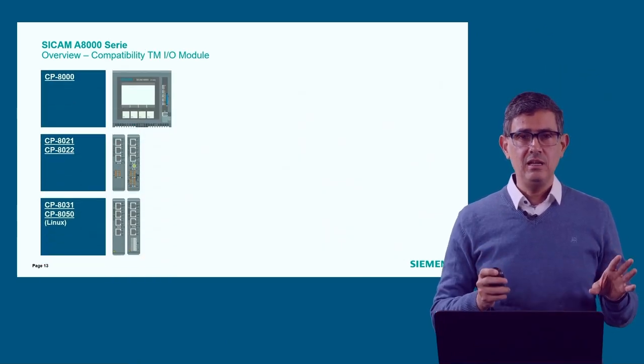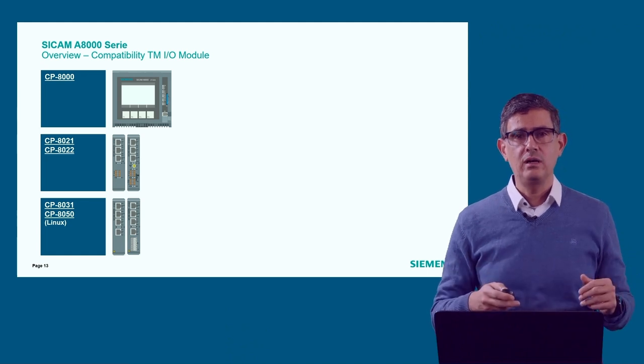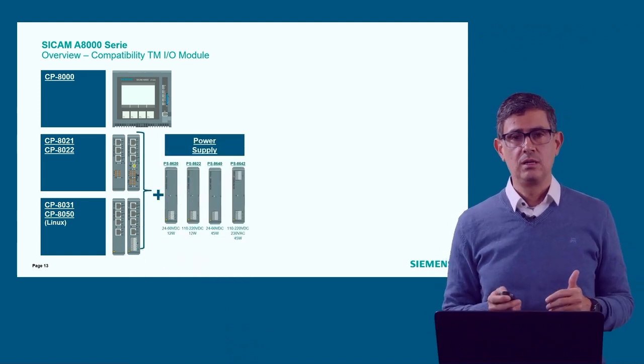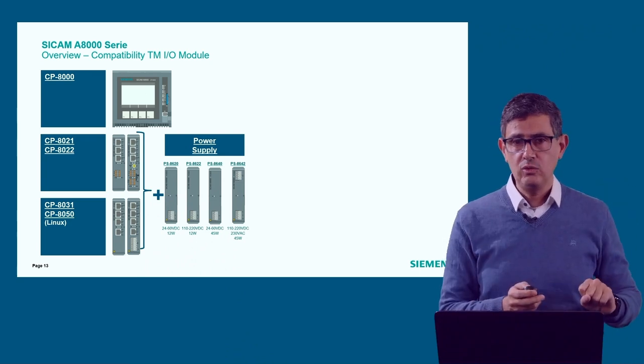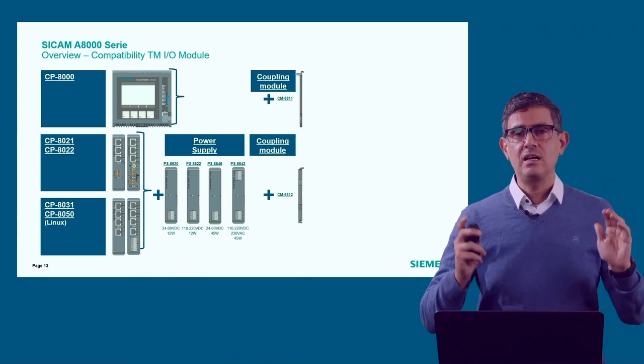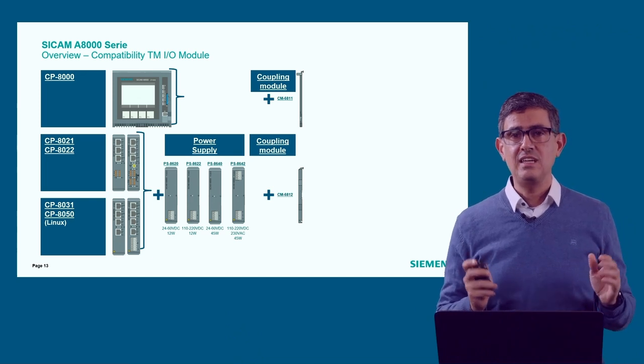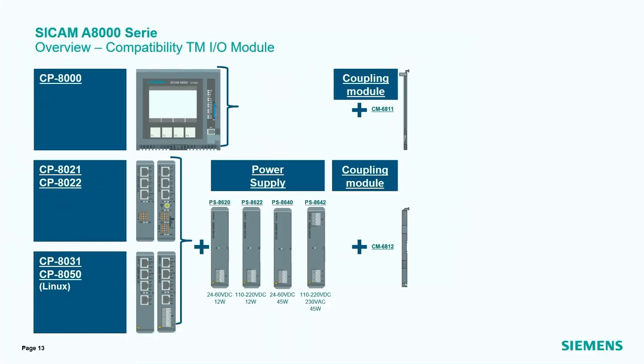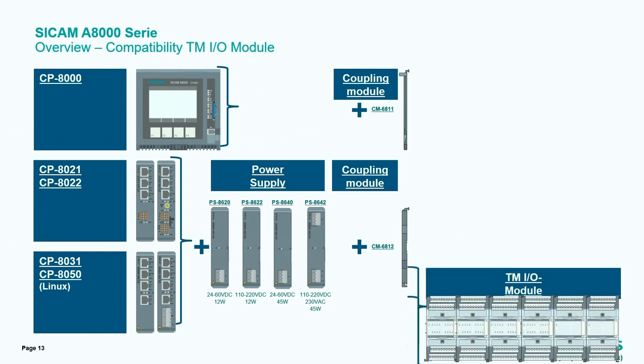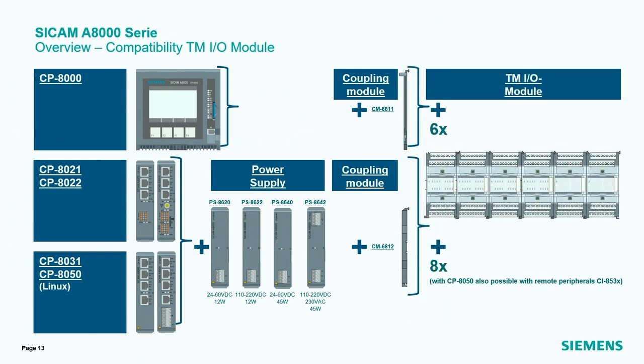Our family of RTUs can also be used to modernize older SICAM TM stations. You just need our regular RTU with a power supply and then a coupling module — either the CM6811 or CM6812, depending on your RTU type — and you can connect the TM modules from your older SICAM TM directly to the RTU. No rewiring is needed; you keep the wiring as it was with only small configuration changes, and your system has been migrated with minimal effort and minimal need for new tests.